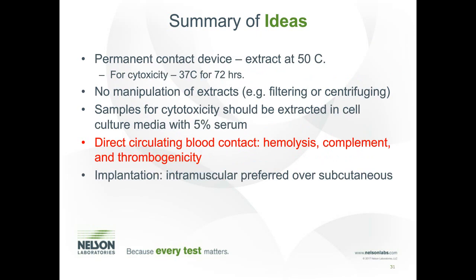Some more summary of ideas. I'm hoping by now everybody knows that if your device has longer than 72-hour contact with the body, you need to extract at 50 degrees C or higher. Unless your material has a glass transition phase close to 50 degrees C, then we can justify using 37.